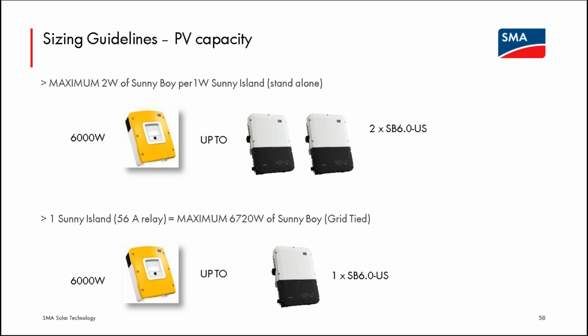So for each Sunny Island, because each Sunny Island has one of these relays that can handle part of the load, no more than 6,720 watts of PV power can be on the protected loads panel. If you have 4 Sunny Islands, that means you can have 26,000 some odd watts of PV power on the protected loads panel. And again, the concern is only when that is grid-tied. If this is an off-grid system, no PV power will backfeed across that relay, because if there's a generator on the other side, the Sunny Island is not going to allow backfeed anyway. So it is only a concern for a grid-tied system, but that is a hard and fast limit.